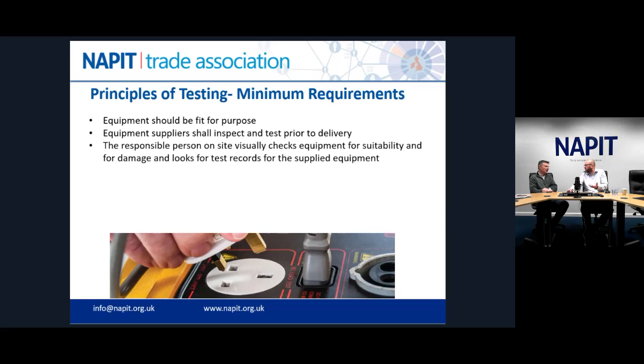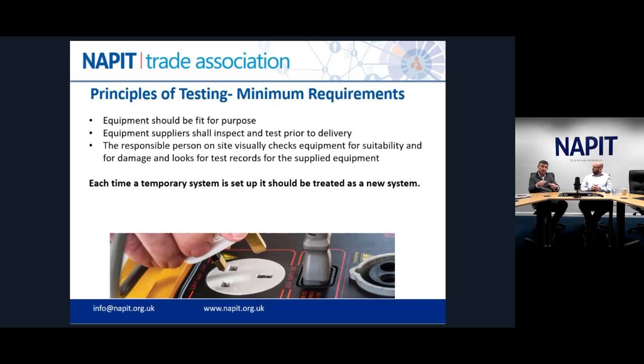Well, I think labels. I think most. It depends on the hire company. Many hire companies might use a coloured cable tie. So when you look at an extension lead, you'll see a purple cable tie, which means that it's in its current period. And they'll say if it's orange or green, don't touch it. Some might just have green labels, traditional equipment tested labels on. Other companies will say, here's a website, there's all the kit that's been delivered to site, go and have a look at our server and check what records you like. So every company approaches it in a different manner, but the key thing is you want to make sure that your supplier is delivering you equipment that's in good order.